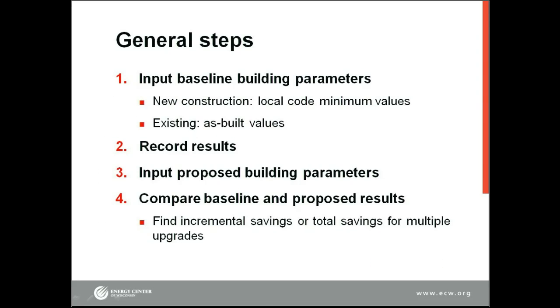What are the general steps for using the back-of-the-envelope calculator? Step one is to input your baseline building parameters. For new construction, that usually means inputting the local code minimum values. For an existing building, that means finding the as-built values and entering them. Once you have your building baseline established, record the results for later comparison purposes. Step three is to input the proposed building parameters — what upgrades are you willing to make to the building, and how will they affect the resulting energy and cost? Then record the proposed building results and find the incremental savings between the baseline and your proposed. You can look at individual measures and find their incremental savings, or look at a host of measures and find how those multiple upgrades affect the building energy use.